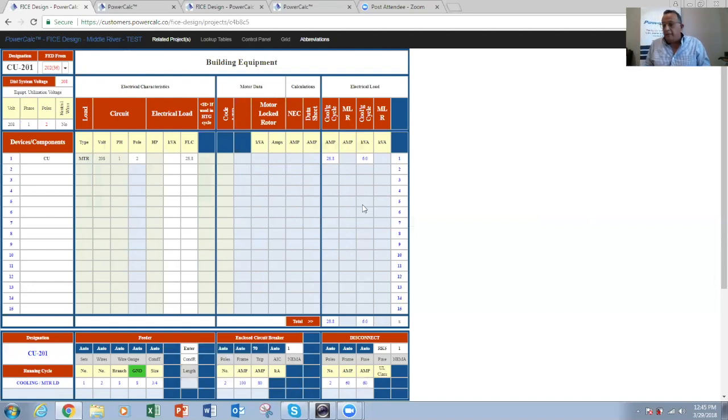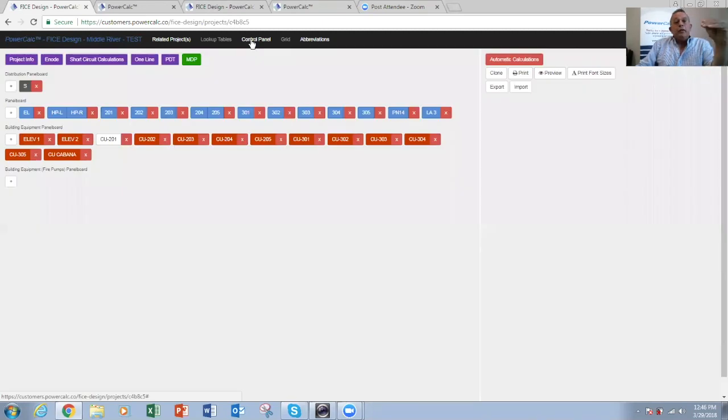That is correct. And if it's a service conductor or a separately derived ground, it would be based on NEC 250.66. The common ground conductor is based on the circuit breaker size, but if the conductor for the branch circuit gets adjusted for a voltage drop calculation and you need to increase that size, say by 20% or 5%, you would have to use the same ratio and increase the ground conductor.